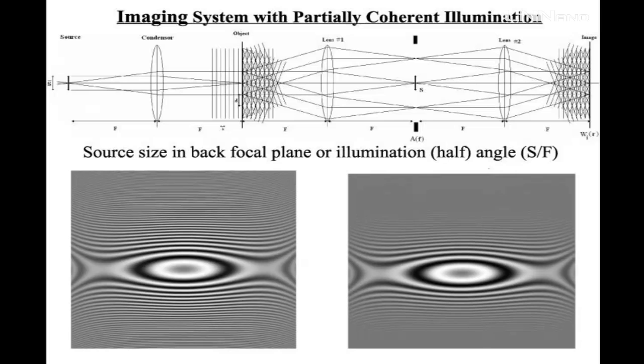But if you have partial coherence, it will then actually disappear from the data because of the integration over the source. And that is not just a matter of resolution, because if you are far out of focus, then yes, it will suppress that information. If you're close to focus like here, it has a very small influence. So this is for biological specimens where you need to go far out of focus in one direction to have enough contrast, and it is an important issue, because you lose the high resolution information. If you want to have 3 angstroms information, then the partial coherence is maybe limiting your system.